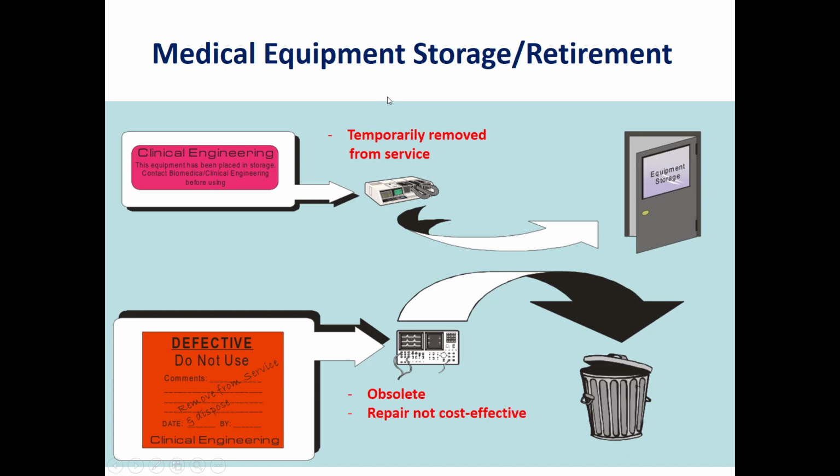Finally, I will cover the last policy and procedure in the management phase of the medical device, which is related to the storage or retirement of a medical device. Some devices could be temporarily removed from service due to a failure or some defect in it, or could be completely removed from service due to being obsolete.